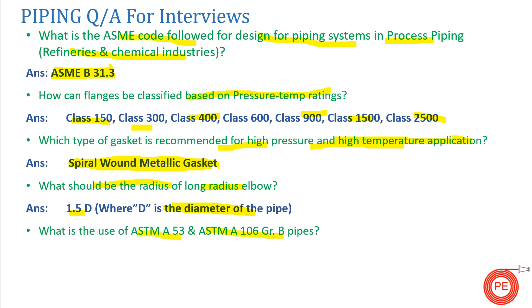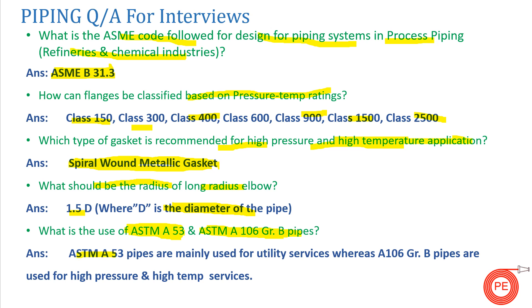What is the use of ASTM A53 and ASTM A106 grade pipe? ASTM A53 pipes are mainly used for utility services — water, compressed air, low pressure nitrogen, or low pressure oxygen. For high pressure and temperature services, we go for ASTM A106 grade. These pipes are carbon steel and are selected for steam and other high pressure, high temperature services.